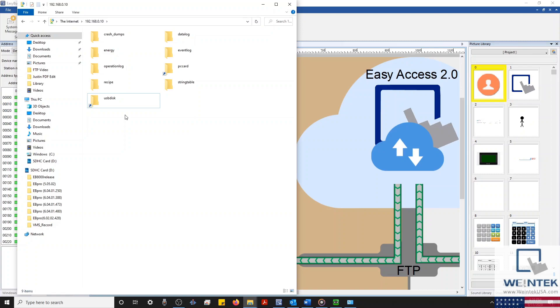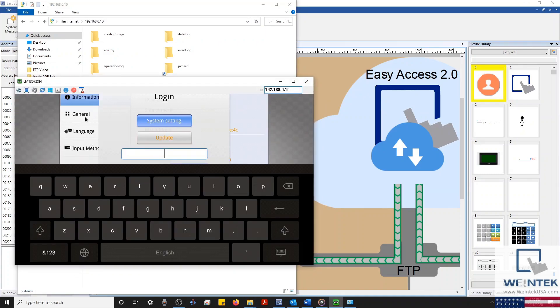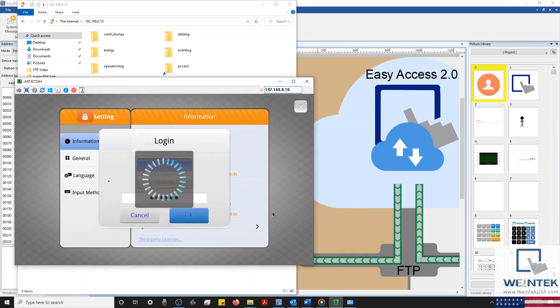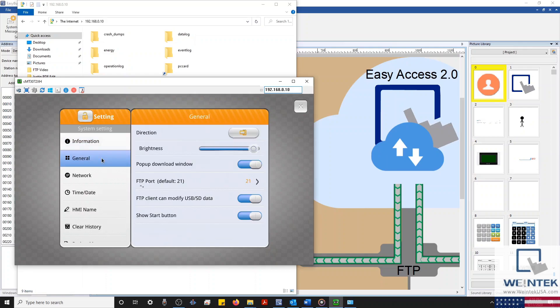In some applications, you might also need to send files to a USB or SD card. By default, an FTP client is not allowed to edit files within the HMI's external memory. However, this feature can be enabled from within the general tab of our CMT series HMIs, or from within the second miscellaneous tab of our non-CMT series.